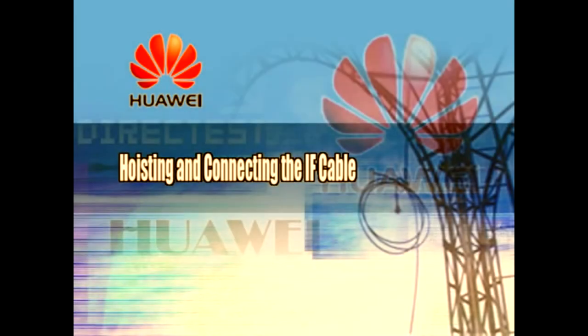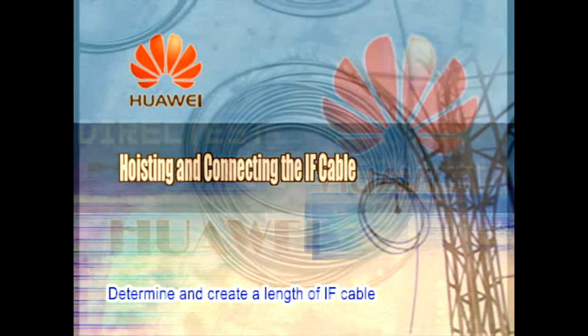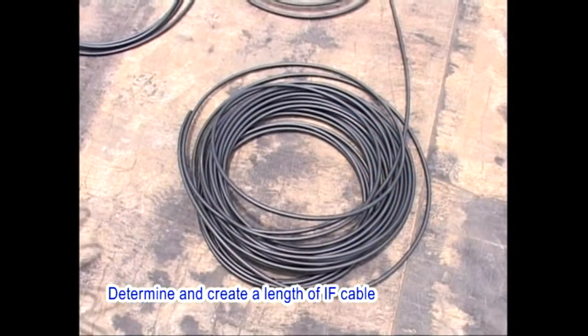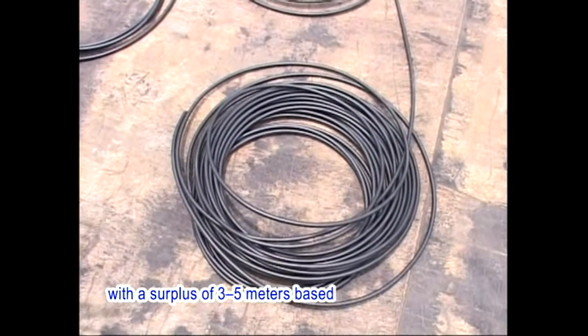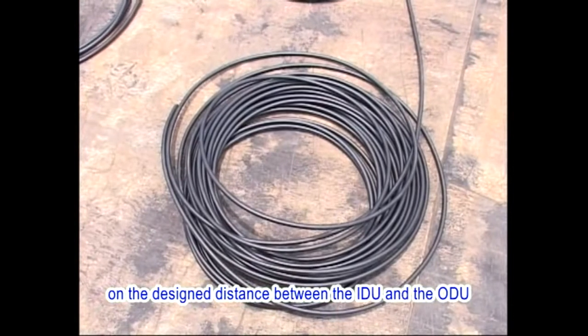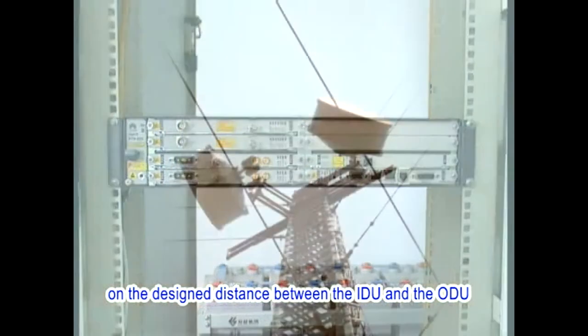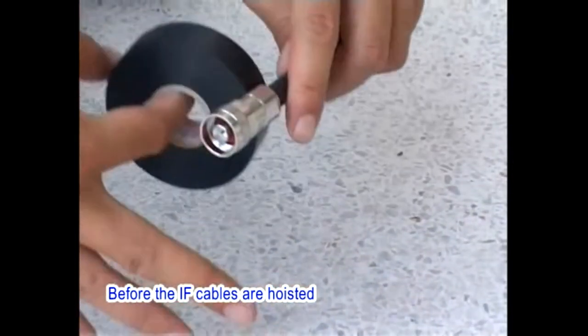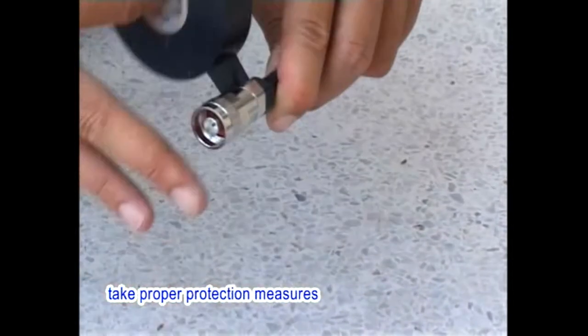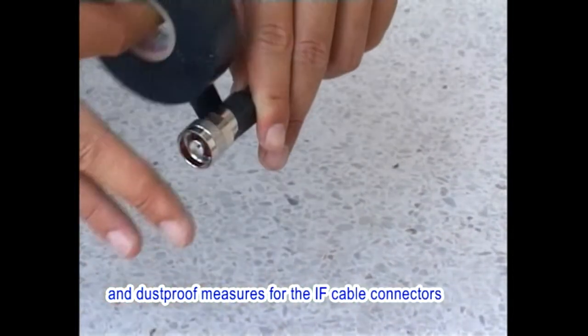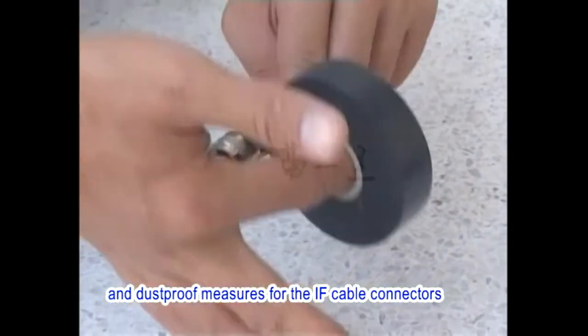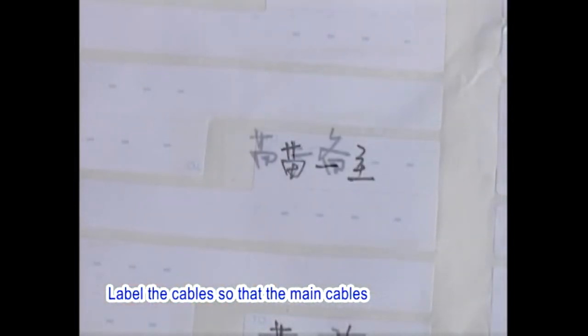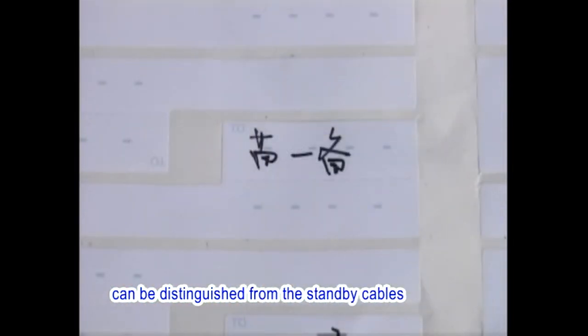2. Hoisting and connecting the IF cable. Determine and create a length of the IF cable with a surplus of 3 to 5 meters based on the designed distance between the IDU and the ODU. Before the IF cables are hoisted, take proper protection measures and dust-proof measures for the IF cable connectors. Label the cables so that the main cables can be distinguished from the standby cables, and there is no confusion when IF cables are connected.